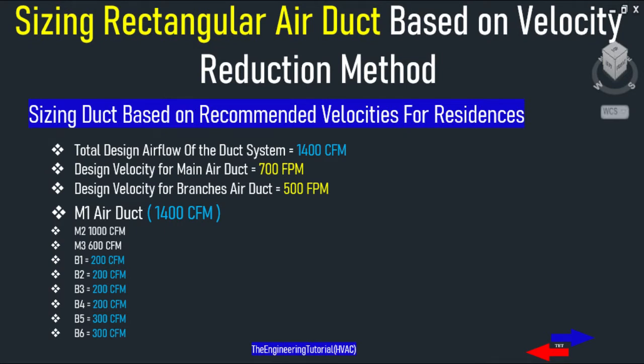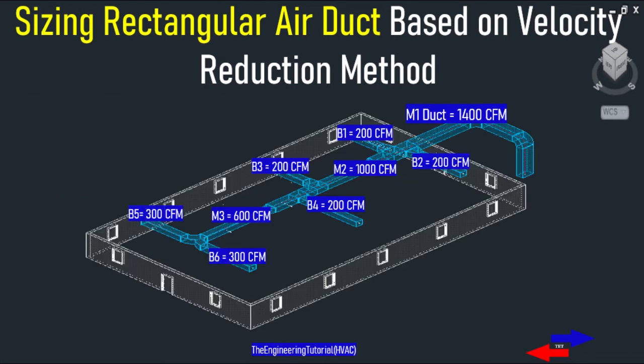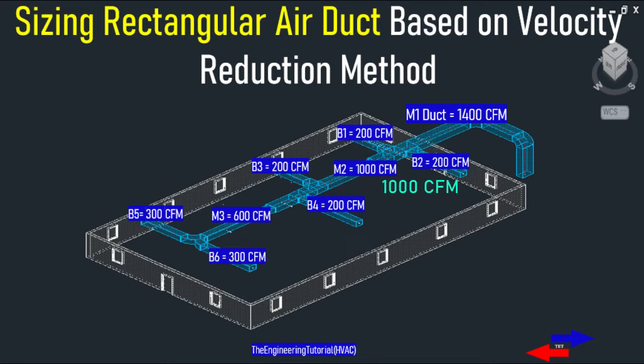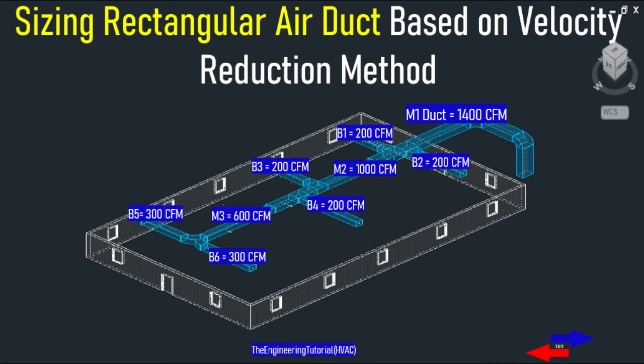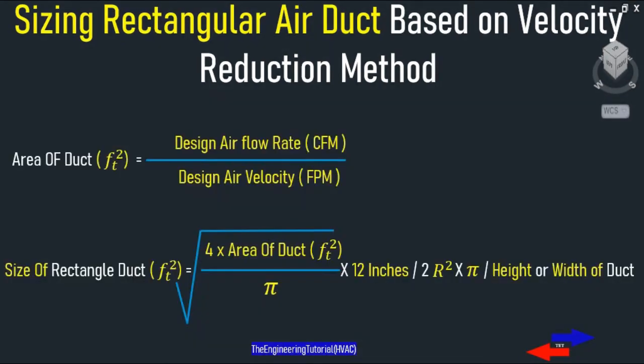For example, there is a design air flow rate of 1400 CFM, and we have been asked to find the sizes of a rectangular air duct for design recommended velocities of 700 FPM for main duct and 500 FPM for branch duct. In the example, 1400 CFM flows through the main duct, minus 400 CFM for B1 and B2, which leaves 1000 CFM for M2. Again minus 400 CFM for B3 and B4, which leaves 600 CFM for M3, minus 300 CFM for B5 and 300 CFM for B6.